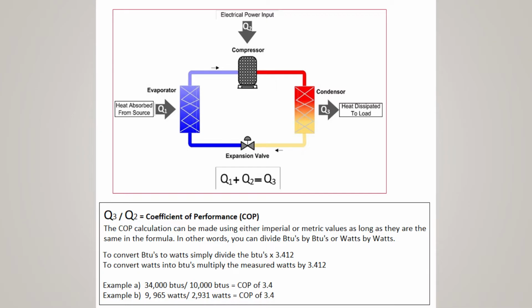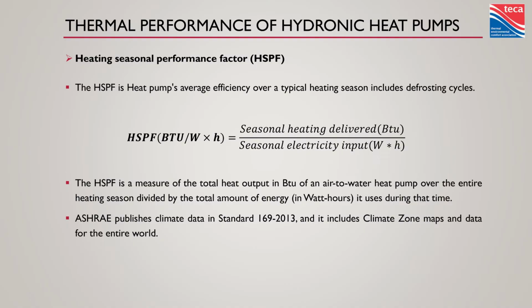So you now know what you're delivering. Grab your amp meter, put it on the compressor, grab your voltmeter, measure the ingoing voltage, and now you can figure out how much energy is being consumed. You, right there with a couple gauges and one relatively inexpensive multimeter, can now calculate the efficiency of these things. So it's great to do when you install them to set a benchmark. Make sure you haven't missed something, but also know how it was performing when you left it, so when you come back to check on it, you know if things have varied.